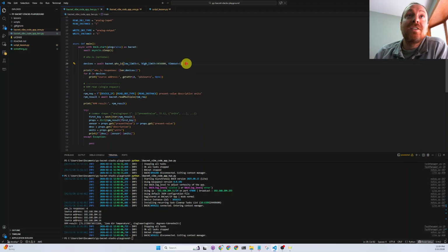So if someone is doing whois every minute, every 60 seconds, every 15 minutes, that's going to congest the network. It could cause problems. Hopefully not shut down the HVAC system in the building, but you really shouldn't be using this beyond the setup of building automation and IoT.